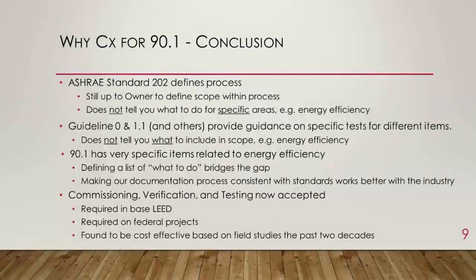So again, in conclusion, we do have ASHRAE Standard 202, which defines the process for commissioning. However, at least my best understanding of Standard 202 is that it's still up to the owner to define the scope within the process. In other words, what actually gets commissioned. So 202 does not tell you what to do for specific areas, for energy efficiency for instance. And in fact, there's not a lot of guidelines there on actual testing procedures to use. Guideline 0 and 1.1 and other guidelines do provide information on specific tests, but they do not tell you what to include in your scope.